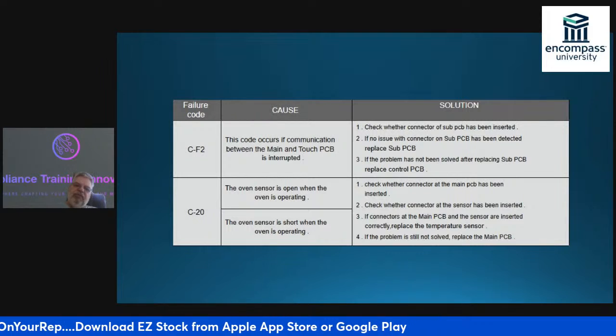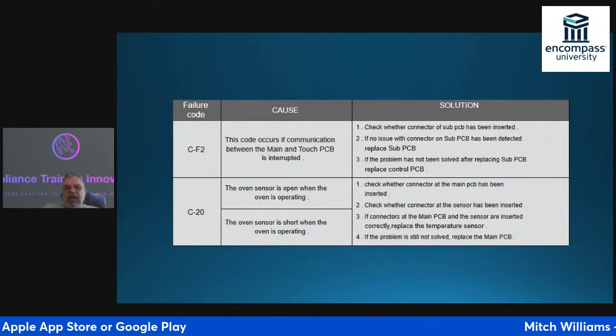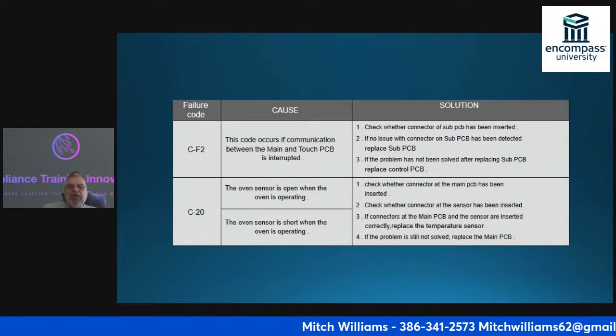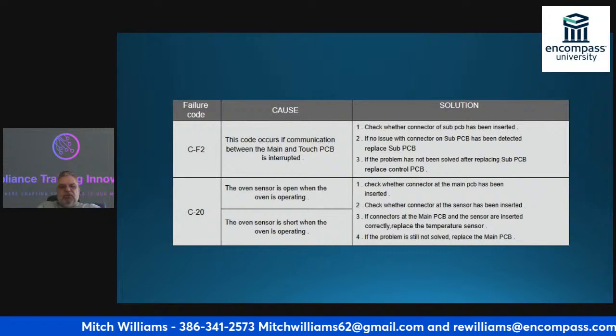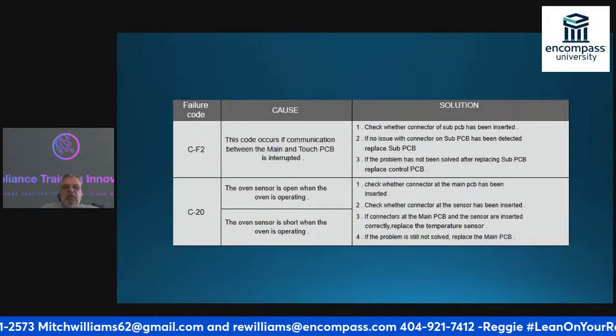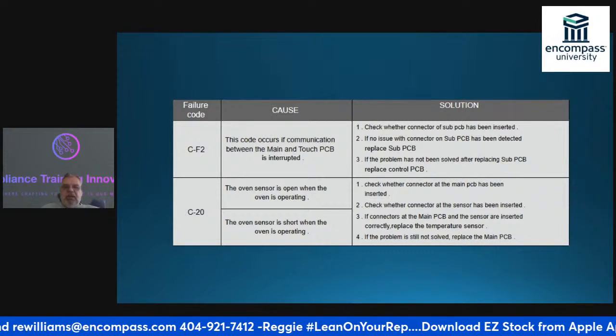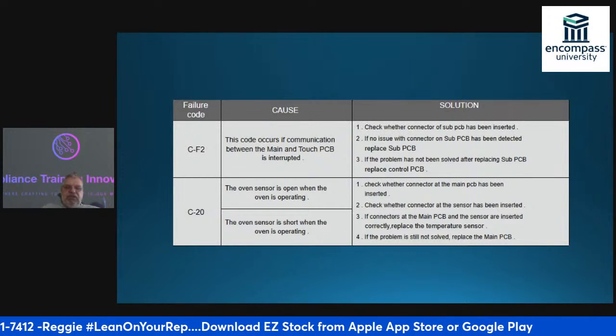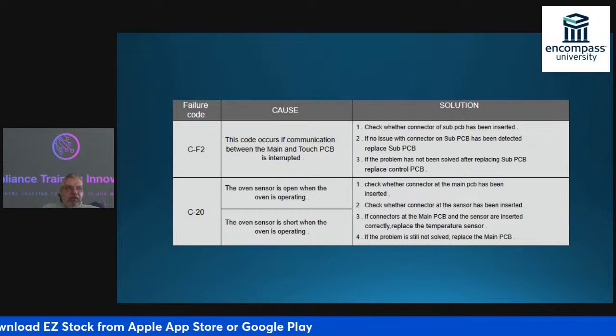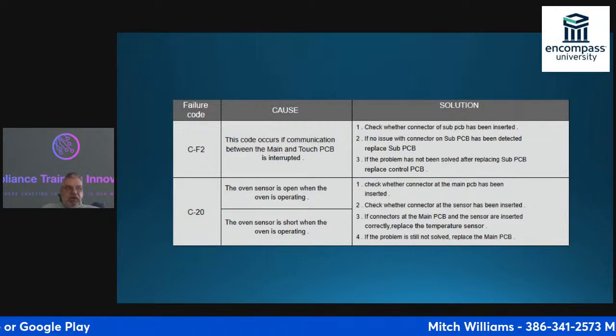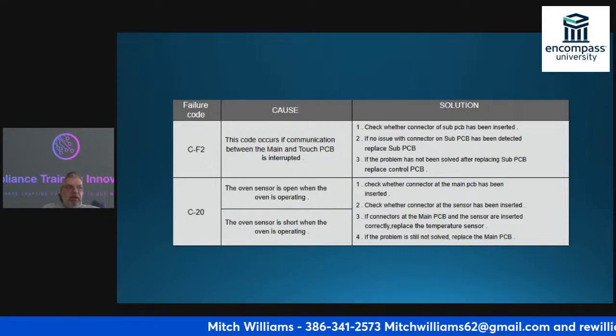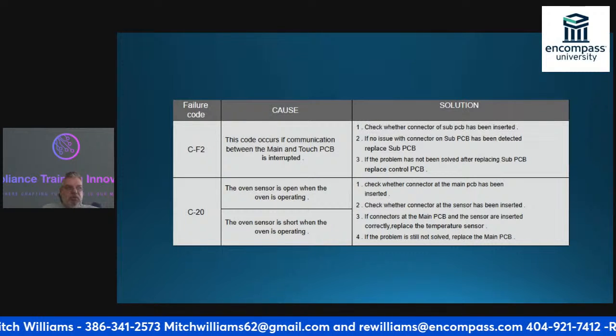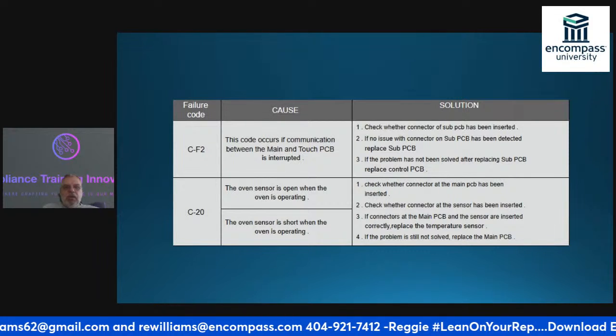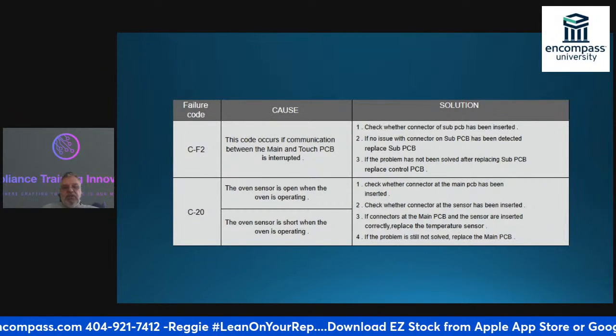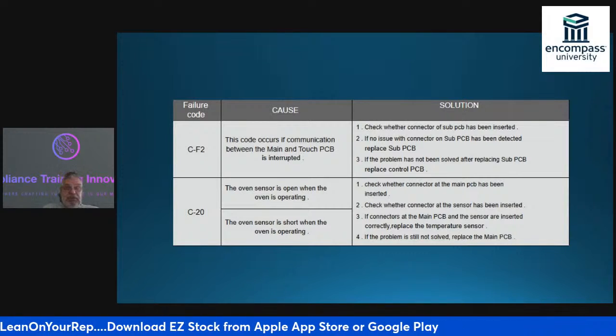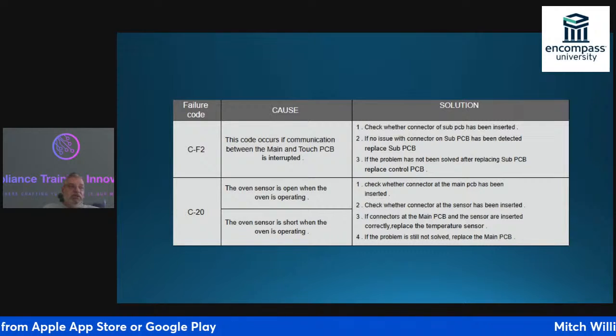So if I get a CF2 failure code and I make sure the connectors are good, as a technician I'm probably going to replace both the sub PCB and the control PCB, or at least order both. A lot of times, once you order an electronic part like this, they will not take it back unless you have a good relationship with your parts distributor. So you want to make sure you've got the part and don't have to come out twice, because if I have to go out three times, I'm losing money hand over fist. So I'm going to order them both.